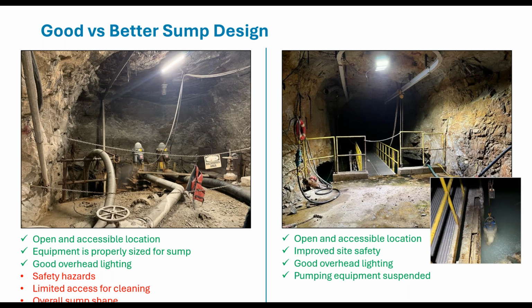Getting into some of the comparisons, good versus better sump design. Here we are looking at two sumps in an underground mine. We'll start with the sump that you see on the left. Essentially, what you can't see in this image is that the sump actually opens up to the left and right below the pumps that you see in the middle of that photo.